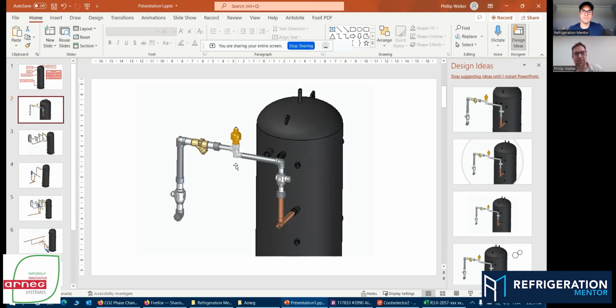And then she's condensing inside the flash tank. So this is what this valve is looking like. We like this valve at a point that's higher. I know you might see the valve a bit lower, but for us, with the way this flash tank is designed, you can see it's slightly higher than the inlet. We do that purposely because we work on basically the same principle as a water column, right? So if you can see my cursor, we're going to say, hey, we've got liquid maximum to about right here. If we have liquid up here, we're going to have a problem because this is our static area. This is our flash gas area. So we're going to have liquid to about up here. We like to put it so she's raised primarily to the same point on the top of the flash tank. Typical flash tank for us is about 90 inches in height.